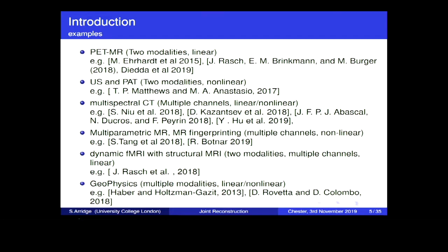Then multispectral CT, there's many talks going to be presented on that here. The difference there is we have not just two. We might say it's a single modality, but it has multiple channels. Some of the arguments purely based on joint geometric considerations are not so easy to apply. Multispectral CT might be treated linearly, if you think of it as just a set of coupled radon transform inversions, but they are coupled in a nonlinear way through the material components and spectral sensitivities. There are several different approaches which may be taken there between linear and nonlinear approaches. You can do it either purely in the data space, unmixing the channels followed by a linear reconstruction, or you can do linear reconstruction followed by unmixing in the image space, or you can do it in a joint fashion.